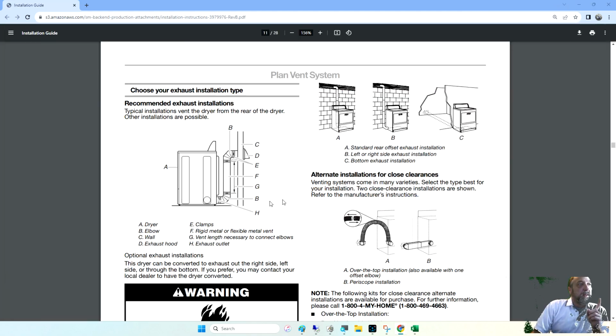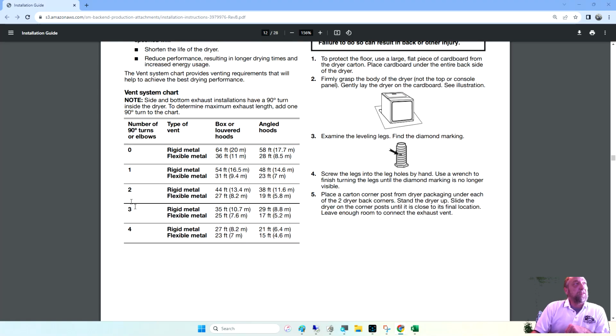Now the importance of this is in this information right here. If we're talking about a rigid or flexible metal hose, not the accordion-looking one, but the metal hose that flexes a little, they say you can go up to 64 feet, but that's with no 90-degree elbows. If we add one elbow, we lose 10 feet. If we add 2, 3, or 4 elbows, we're down to about 27 feet. That's important, because what if you go into someone's house and they're using the flexible hose, which you're not supposed to use, and it's got 10 twists and turns before it even goes out the back wall? Every turn in that airflow puts back pressure on the dryer fan and makes it harder for it to dry.